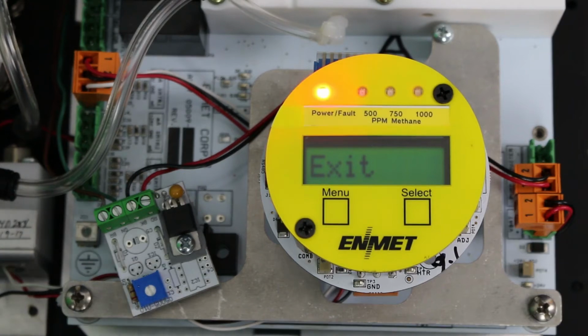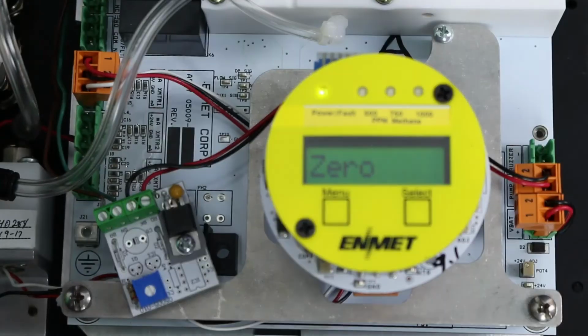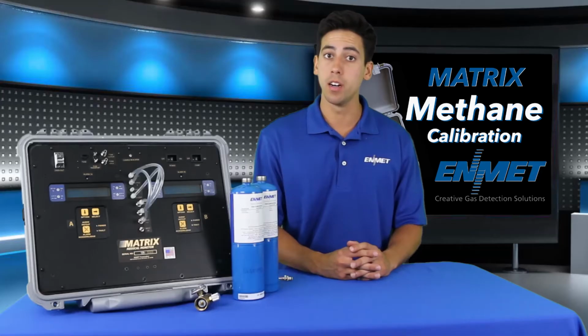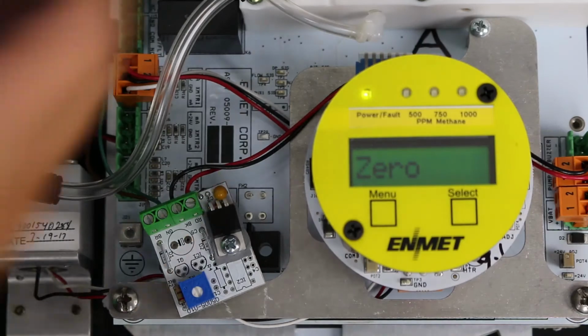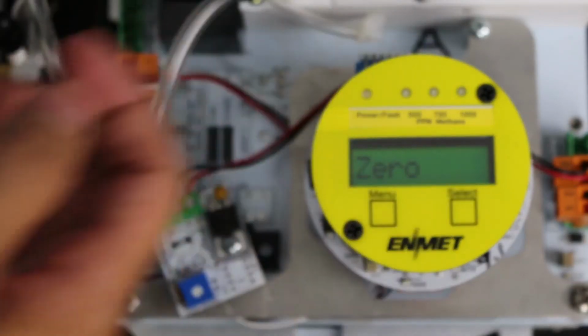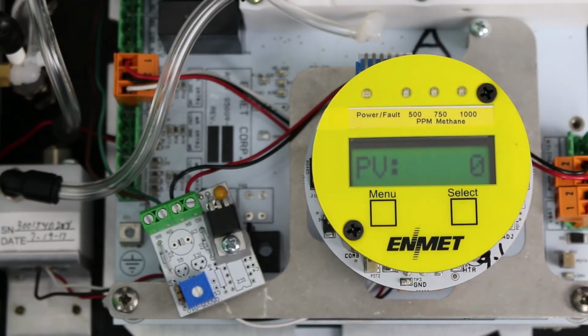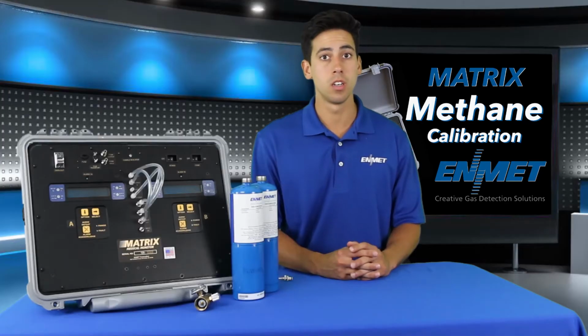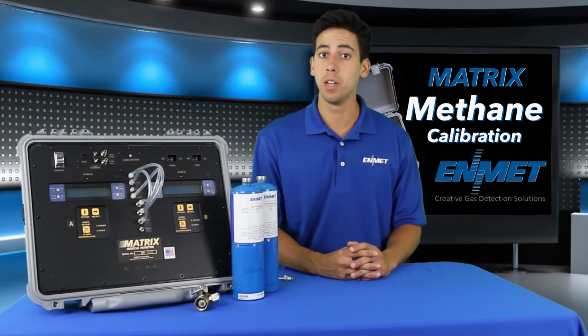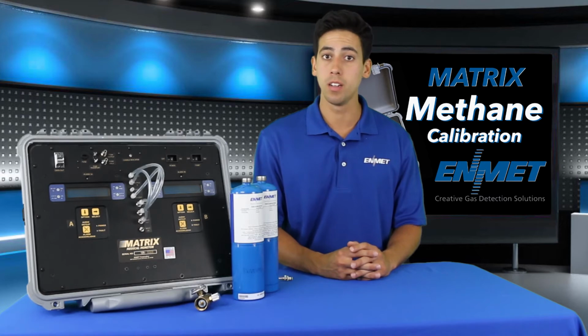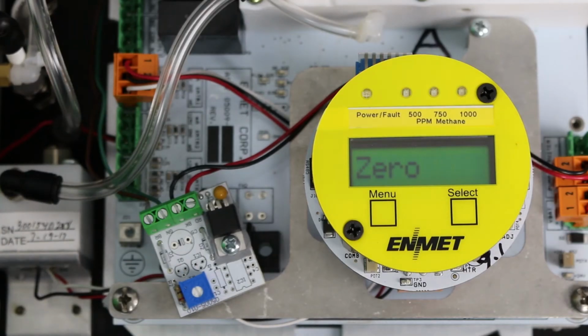Press the menu key once to highlight the zero submenu option. Now you will need to connect your calibration regulator to your zero gas cylinder and connect the regulator tube to the matrix input port for your methane channel and open the valve on the regulator. Press the select button to begin the zero procedure. The display will alternate between 0 and PV. PV stands for present value.